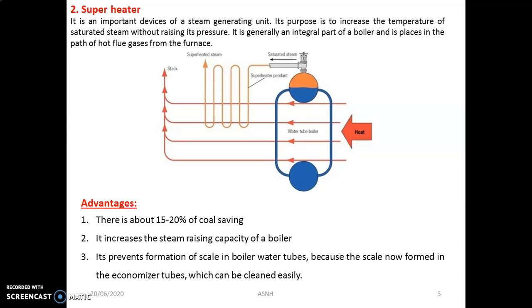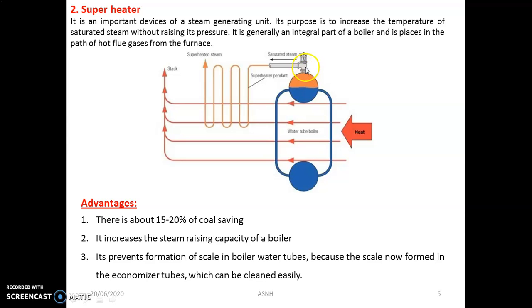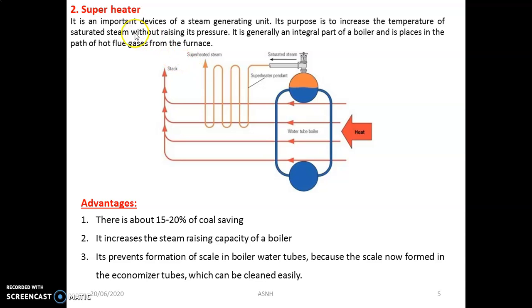The second important accessory of the boiler is the superheater. Why do we need a superheater? It is a very interesting question. In some applications like steam power plants, steam engines, and processing industries, we need more heated steam rather than saturated steam. There are two drums: the lower drum is the water drum and the top drum is the steam drum. After the evaporation process, the steam generated is saturated. We supply that saturated steam into the superheater coils, where it gets heated with the help of flue gases generated at the end of the combustion process, and the coils get heated through those flue gases. At the end, you get superheated steam.